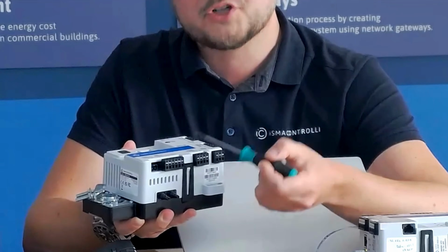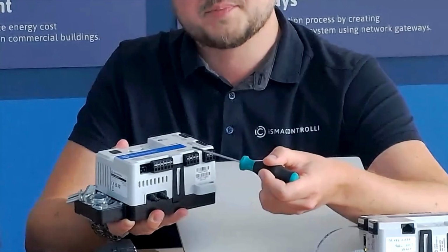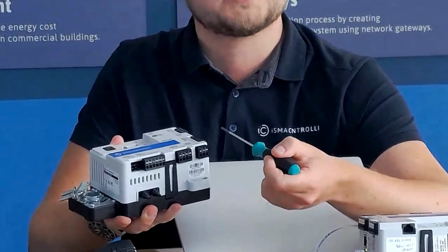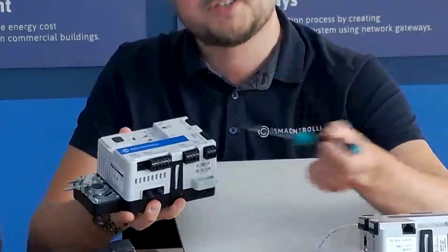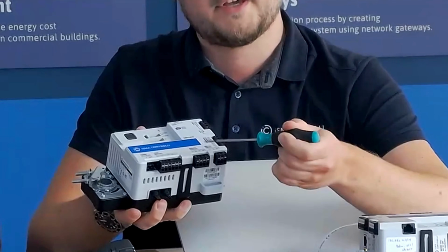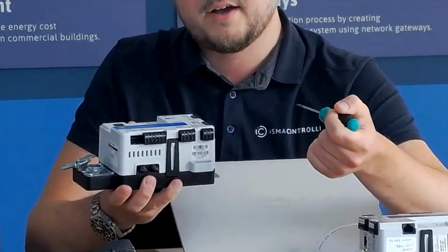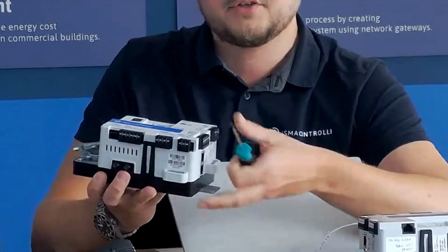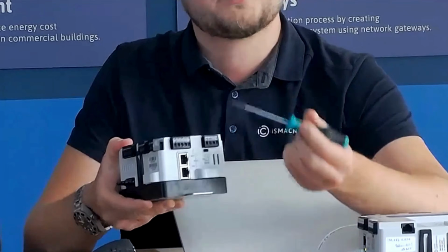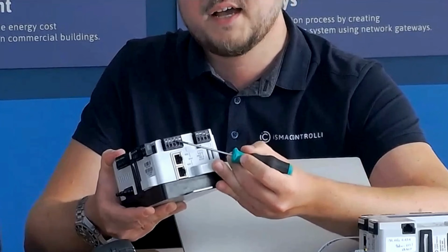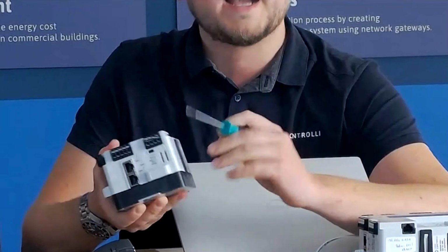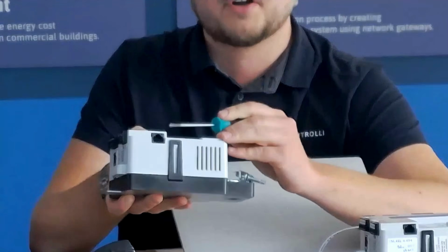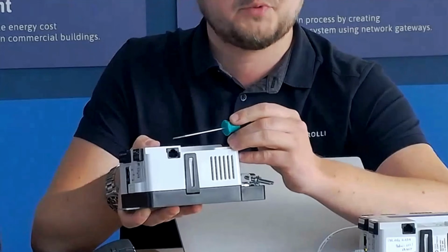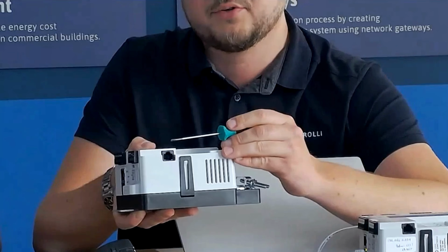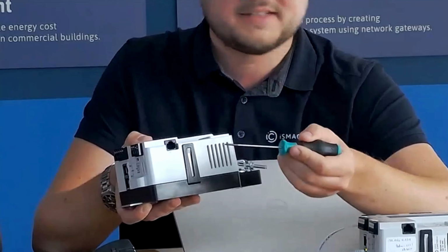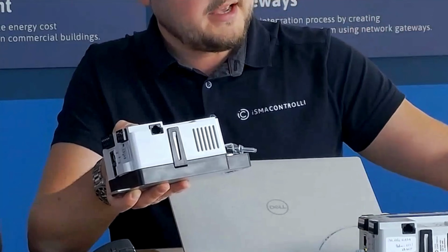We have here 4 triac outputs for the actuators, but the application can also work with the analog outputs. So based on the configuration of the application in the unit, you will wire the controller for the proper actuators. We have 2 digital inputs here. We have the universal inputs, which are configurable for different sensor types. And then we have the COM port, which is shared with our smart plug. The same COM port, which is a BACnet MSTP and Modbus RTU port, will allow you to integrate our wall panels directly. So you always have an option.